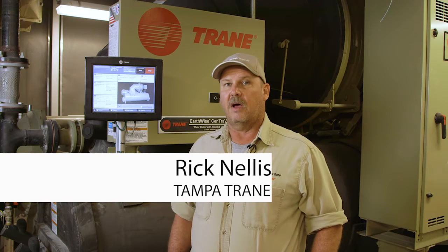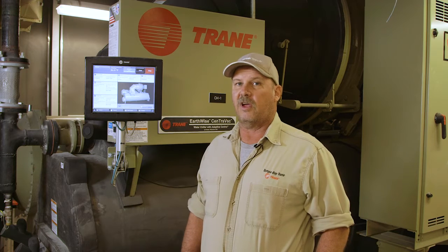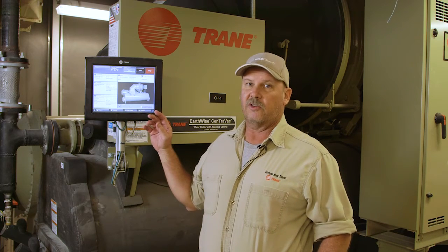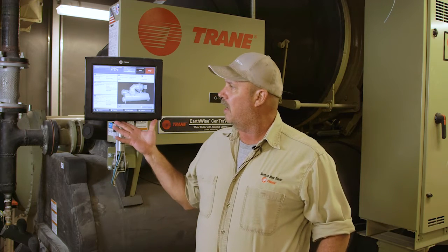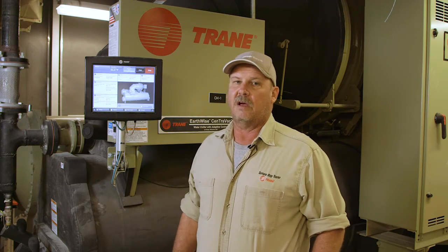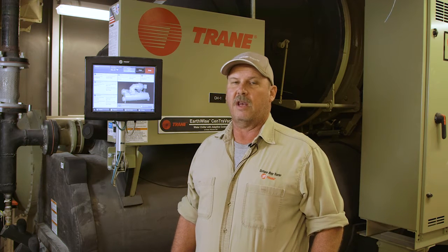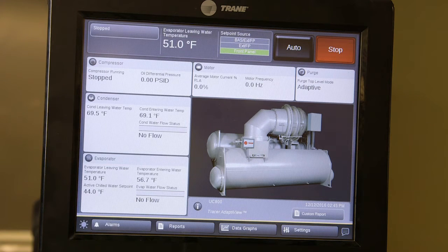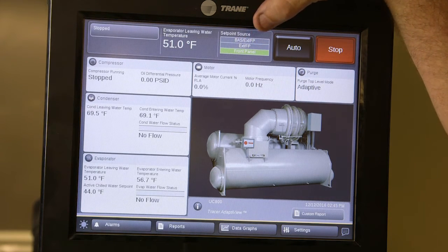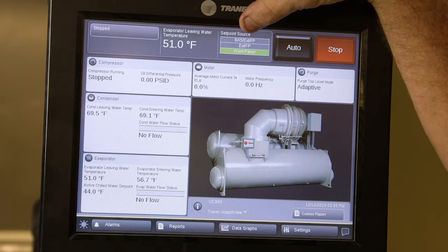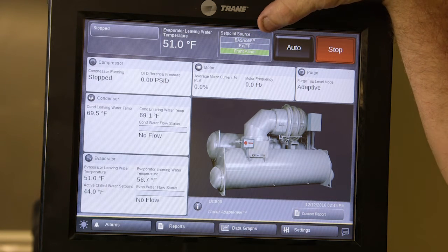This is a Trane adaptive frequency drive chiller with AdaptiView controls. All controls can be managed by the user from the front panel or a BAS automation system, which is covered in another film. This device controls starting and stopping, monitors the chiller, checks how it's running, and records any faults so the user can diagnose and fix problems later. The control panel can start and stop locally or through the front panel. Right now it's set up for front panel control, indicated by the green bar that's highlighted. It can also operate by building automation system, in which case the BAS EXTFP button will be highlighted.